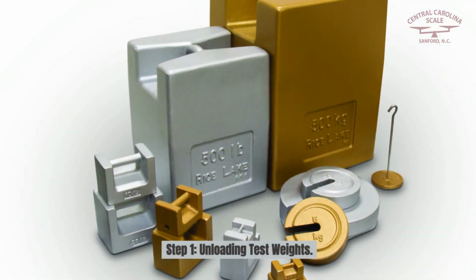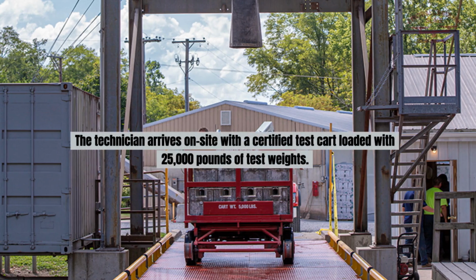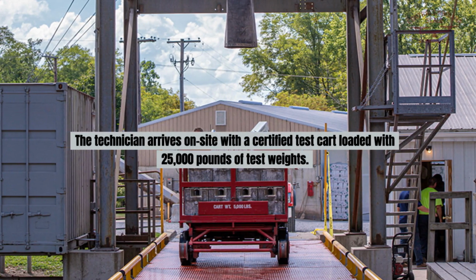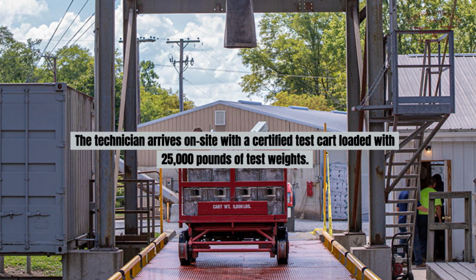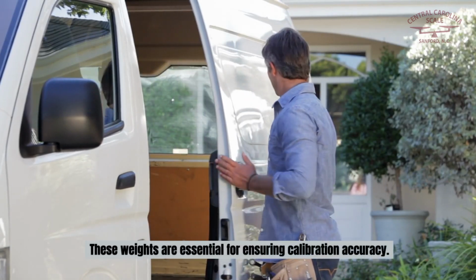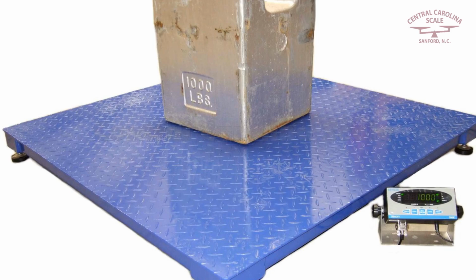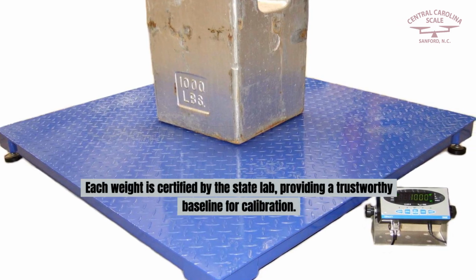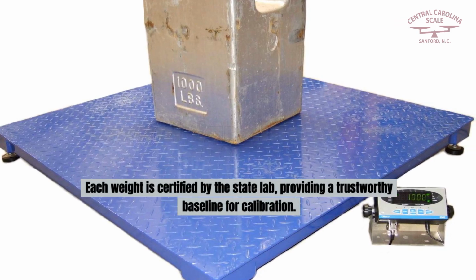Step 1. Unloading test weights. The technician arrives on site with a certified test cart loaded with 25,000 pounds of test weights. These weights are essential for ensuring calibration accuracy. Each weight is certified by the state lab, providing a trustworthy baseline for calibration.